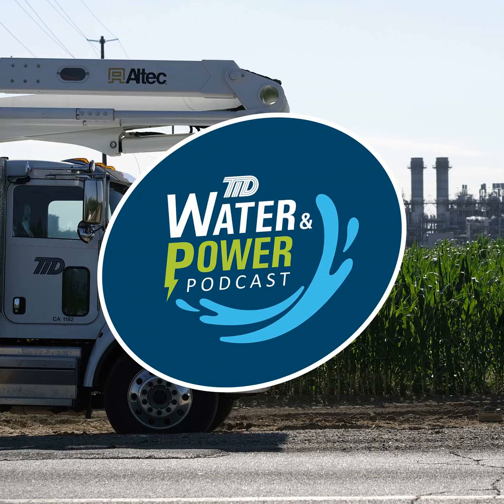When TID is considering new residential subdivisions, like out in the Patterson area, do we plan for a certain amount of redundancy to help maintain reliability? Yes, we do. Every single one of our feeders always has a tie back to multiple different substations, so we can always have the capacity to feed our customers. If one feeder out of one substation needs to be de-energized, for example for maintenance, the other substations attached to that feeder can provide supply. So we have that redundancy there.